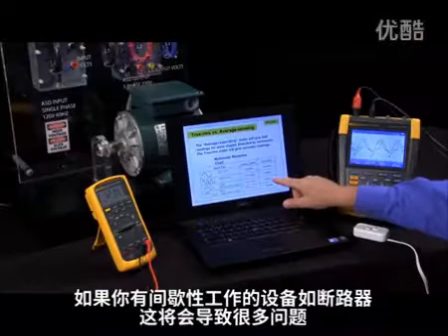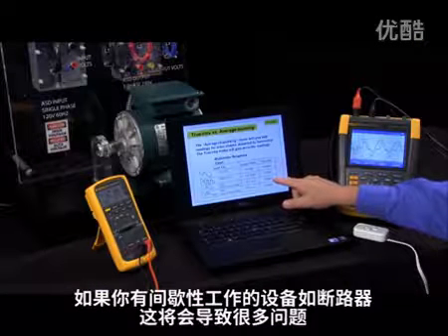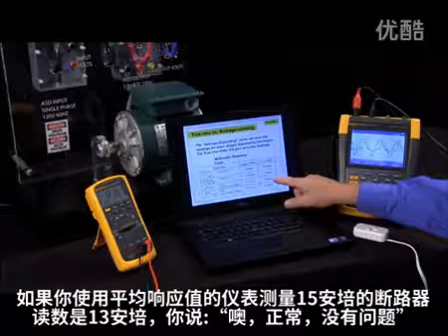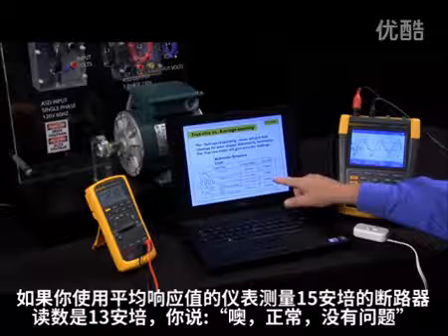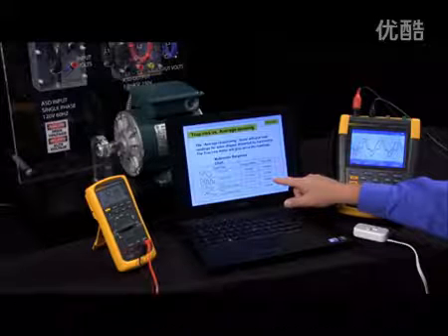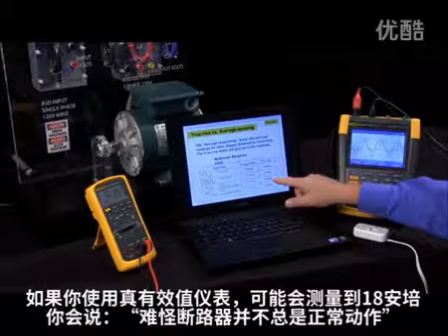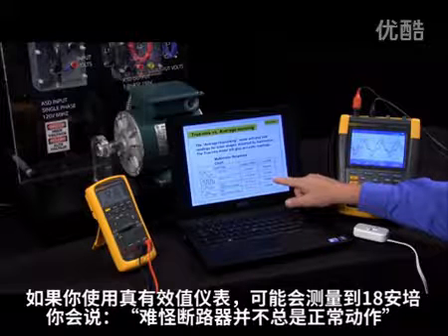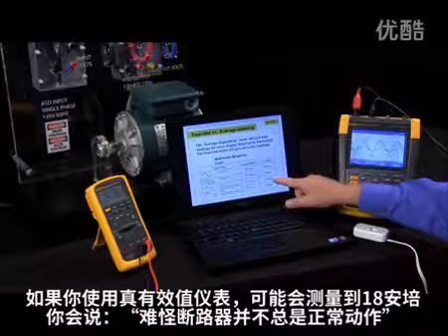This could cause you a lot of problems if you have a breaker that's popping intermittently and you measure it with an average responding meter. You're reading 13 amps on a 15-amp breaker. You say, okay, well that's not the problem. If you take a true RMS meter, you might read 18 amps on that 15-amp breaker, and then you're saying, I wonder why it's not popping all the time.